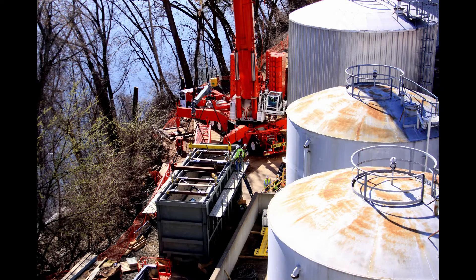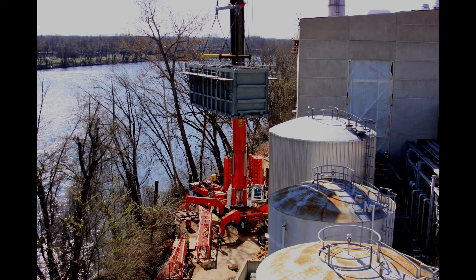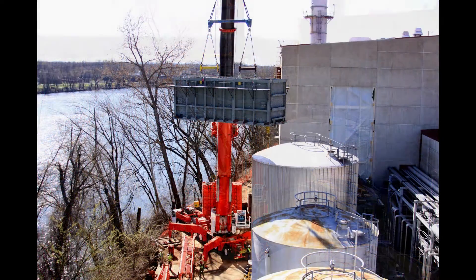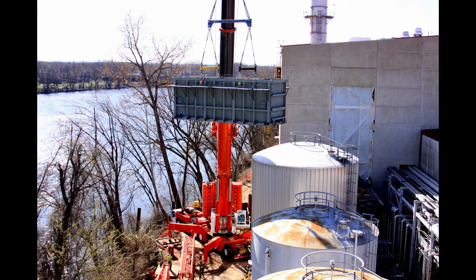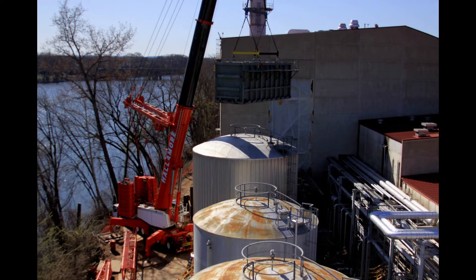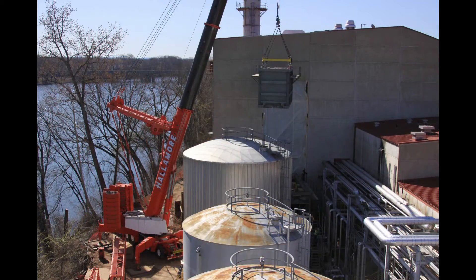We had to drive a pile for each outrigger of the Demag 500, which is a 600-ton crane. Each outrigger got four HP 14 by 73 piles driven down to rock, then a 10-yard concrete cap placed at each location. Once we got those built, we moved on to building the track system, which was another six piles driven down to rock, and about 20,000 pounds of bracing and framing and beams. The boiler modules will all come into the 600-ton crane, get picked, set on the track system, and eventually rolled inside the building onto the new foundations.